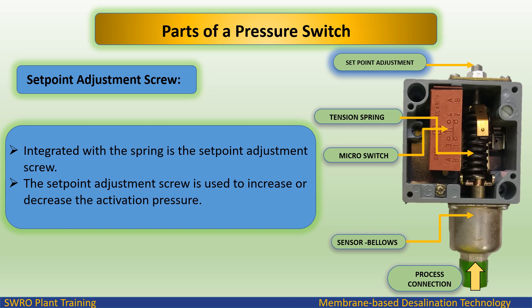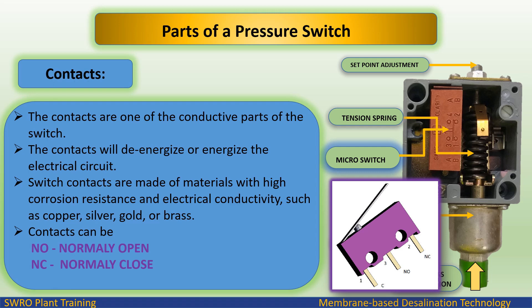Set point adjustment screw. Integrated with the spring is the set point adjustment screw, which is used to increase or decrease the activation pressure. The contacts are one of the conductive parts of the switch; they will de-energize or energize the electrical circuit. Switch contacts are made of materials with high corrosion resistance and electrical conductivity, such as copper, silver, gold, or brass.